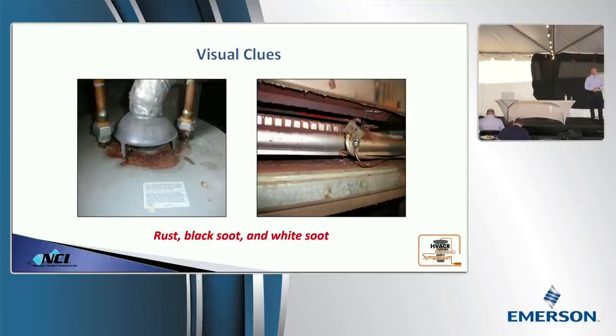You guys see furnaces like that a lot? Tops of the burners all rusted up, all kinds of crap laying in the bottom, pilots all rusted up. You could probably see some signs of rollout around the top of that burner compartment. Looks pretty common, right? That's where Mother Nature's controlling combustion air. Sometimes it may work, sometimes it doesn't. So those are some common signs.